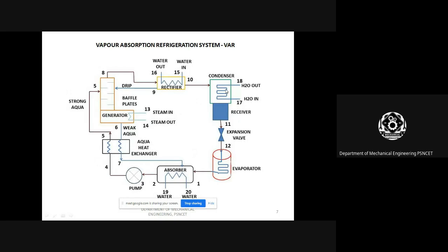The condenser is mainly used to convert the vapor refrigerant into a liquid refrigerant at high pressure and high temperature. Then the expansion valve is used to reduce the pressure and temperature still more. In the evaporator, that liquid refrigerant once again extracts heat from the body and is converted into vapor refrigerant. It is passed on to the absorber, which absorbs the refrigerant, and it is pumped to the generator through this heat exchanger and the cycle is repeated. So this is a general cycle.